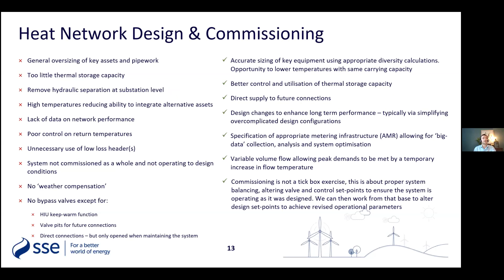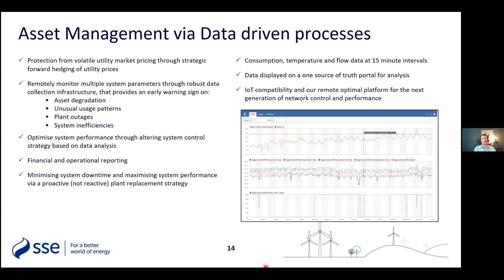Conscious of time, this is an obvious one, but there is so much that you can see from data. If I said to you that we collect a data read from a meter every 15 minutes, we collect 4 different points of data: consumption, flow rate, flow temperature, and return temperature every 15 minutes from every meter, and that costs us around €7 per meter per year. It's really such a low cost, yet you can see so much from it, down to individual apartments. We can see if a valve is failing, if a strainer is blocked, just by those 4 data points. So definitely something to consider.